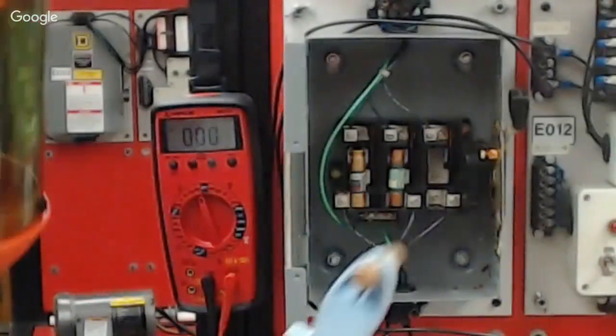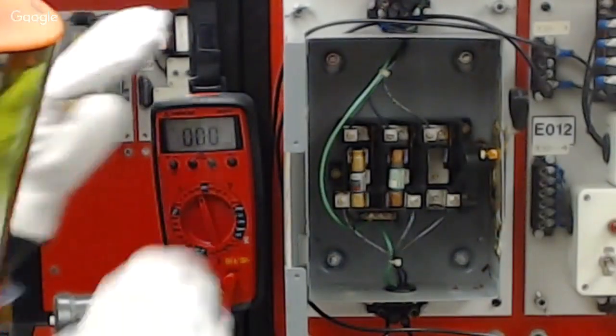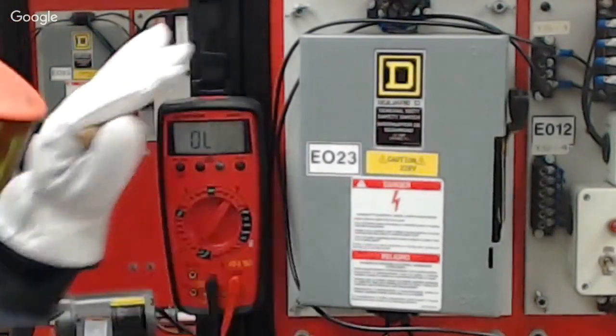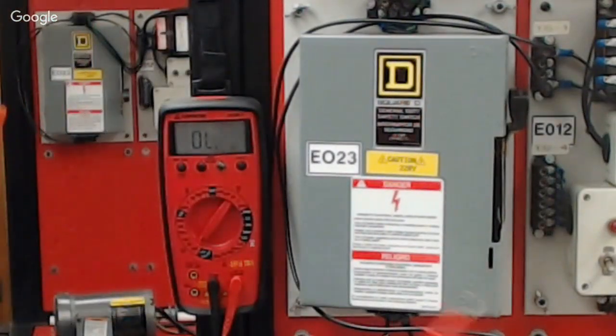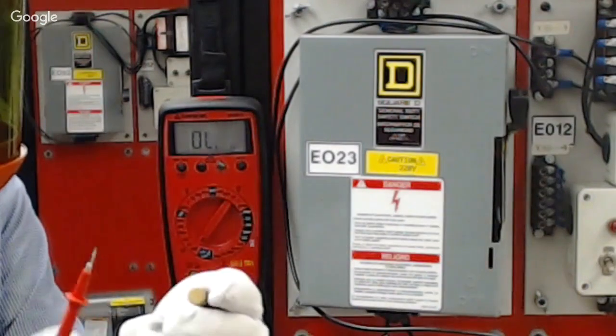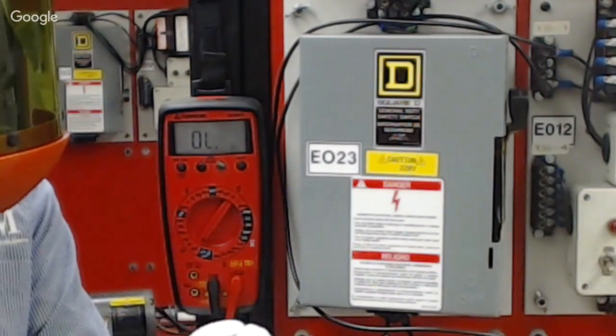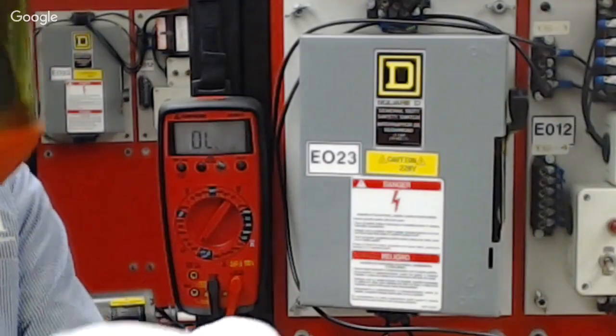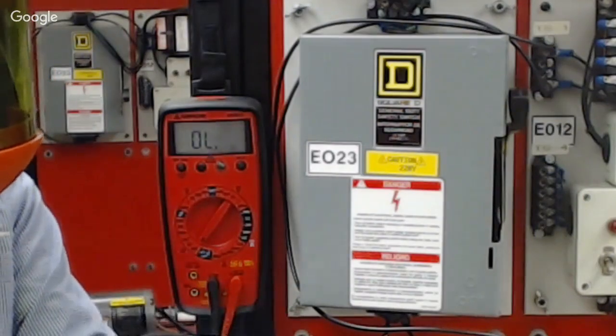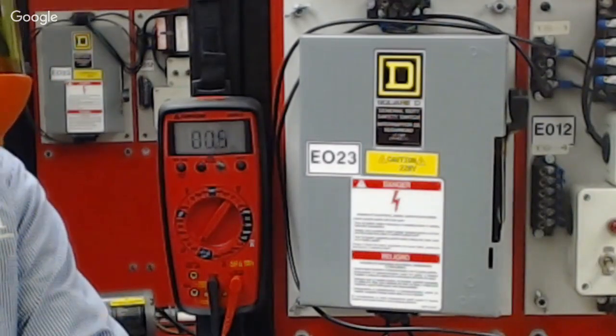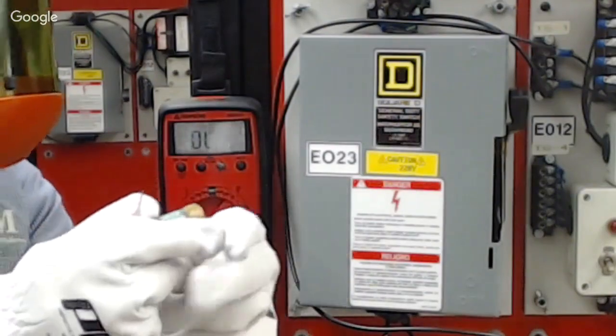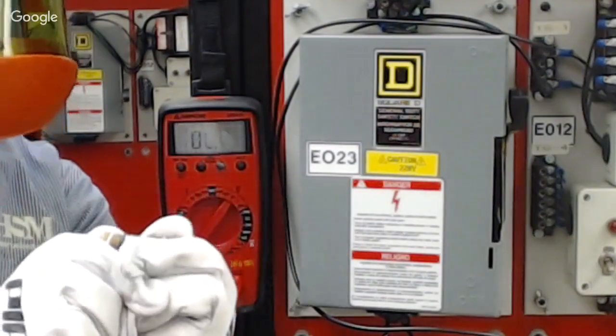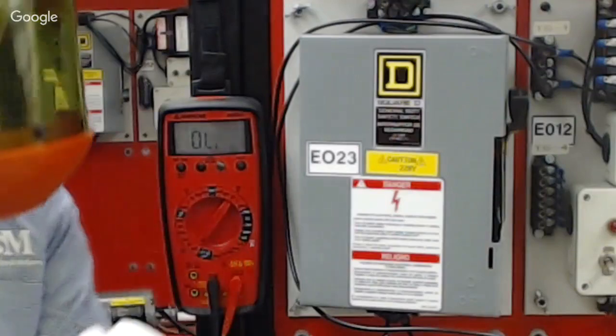Firmly grasping it, I can turn my meter over to ohms. You have to apply a firm grasp to this to make sure you get through there. And we'll see that first I want to check my meter to make sure my meter is working. And my meter is working. I want to grasp the fuse and check it. And I'll see that that fuse is open.